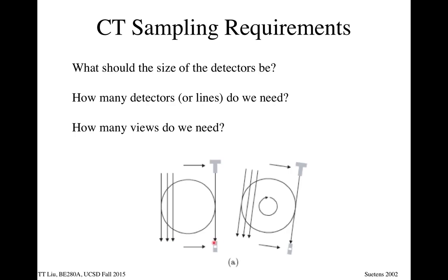So yeah, we have the width of this detector. We make this thing 50 microns wide, so it's looking at a very narrow line through the sample. And then we also discussed, but we didn't do it in detail, the fact that unless the X-rays are coming from a point, we have a problem: say the X-rays are coming from a very wide source. The X-rays from over here can pass through and hit our detector, and X-rays from over here can pass through and hit our detector. So that also blurs the picture, and that's the spot size.